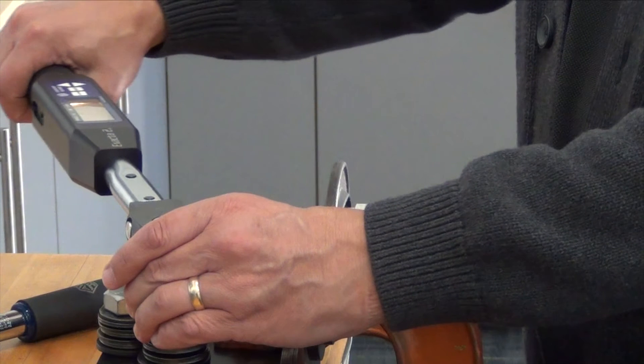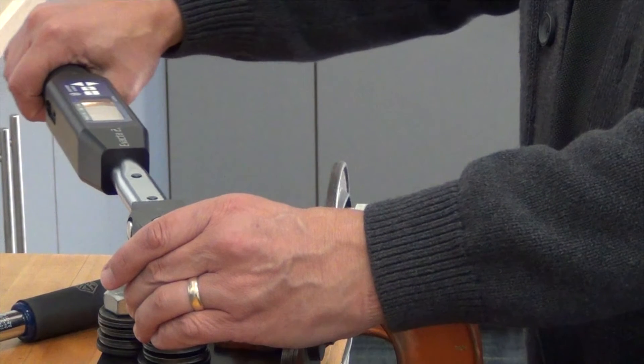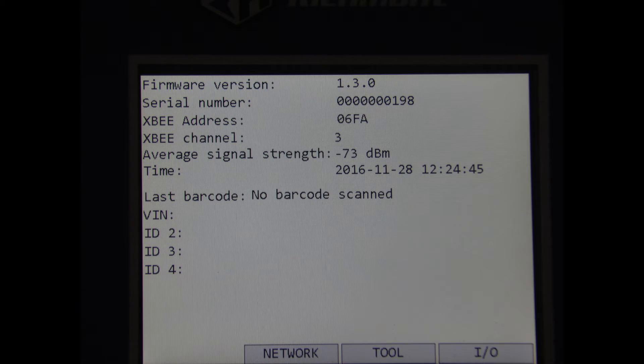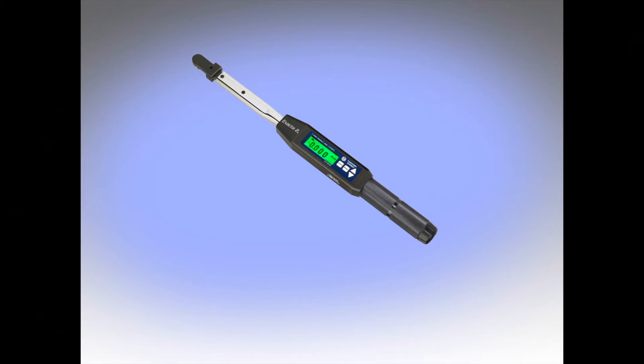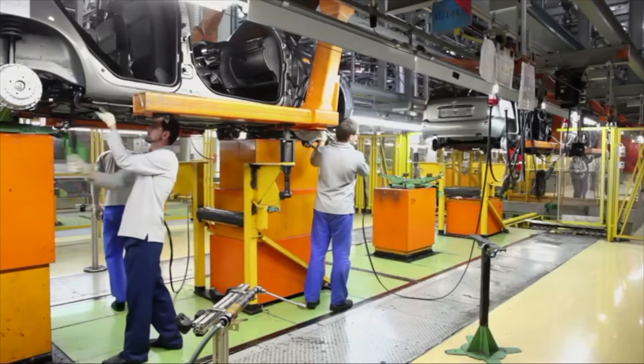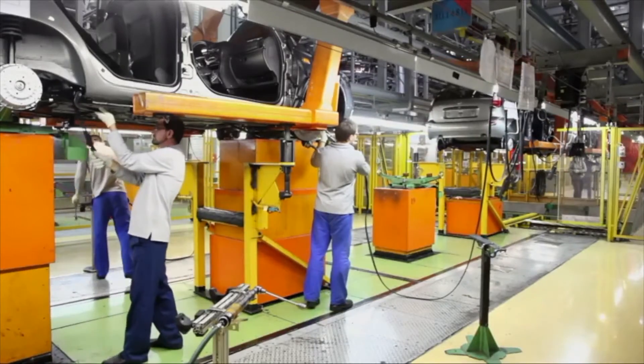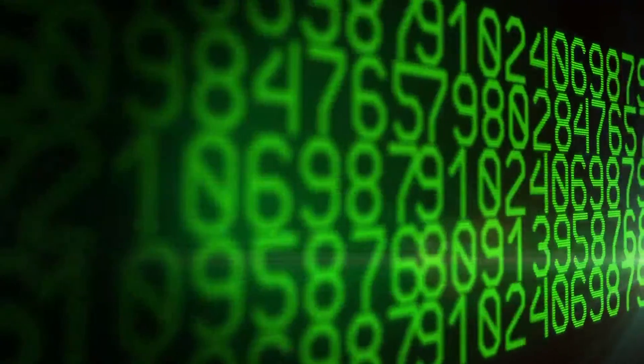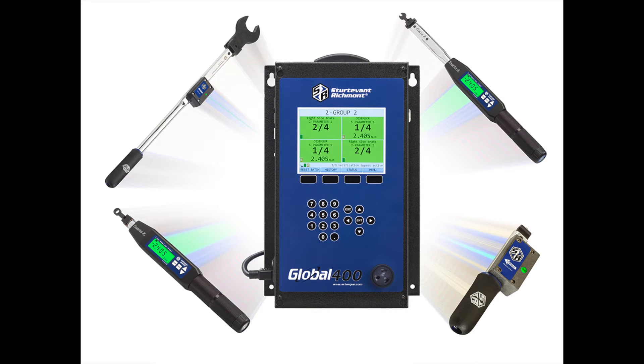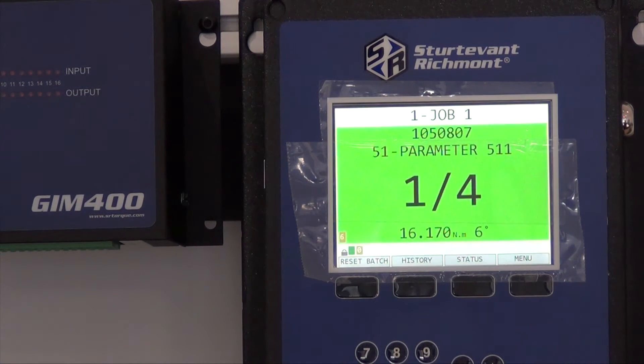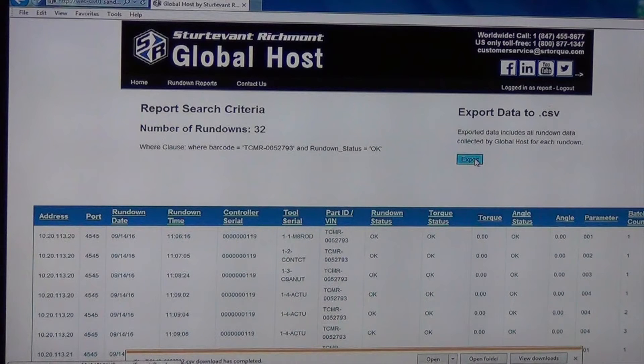If the radio connection between a Global 400 and a 1200 series Exacta 2 or a 1250 series Exacta 2 digital torque wrench is severed, the operator continues to work, and when the radio connection has been re-established, the wrench sends all the batch data back to the Global 400. The Global 400 updates the MES and/or the data repository. Everything is accounted for — we call that accountability.